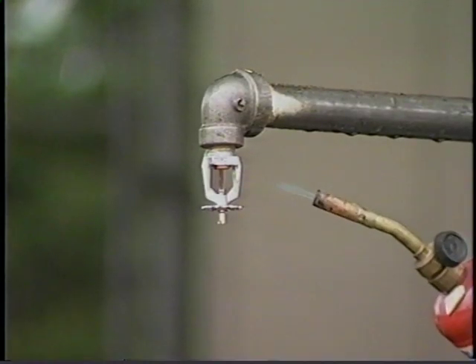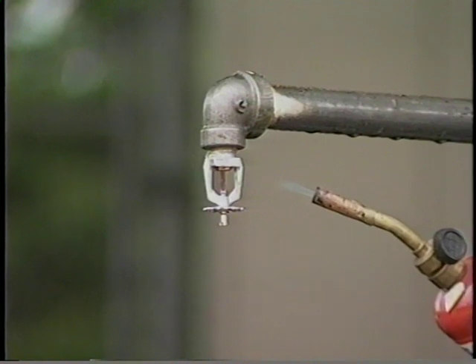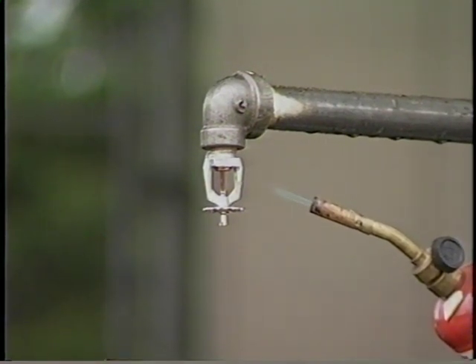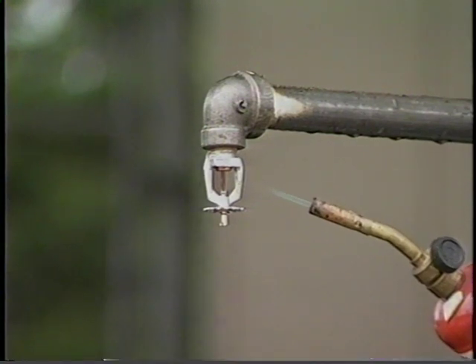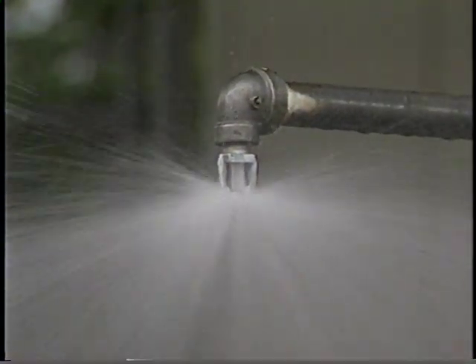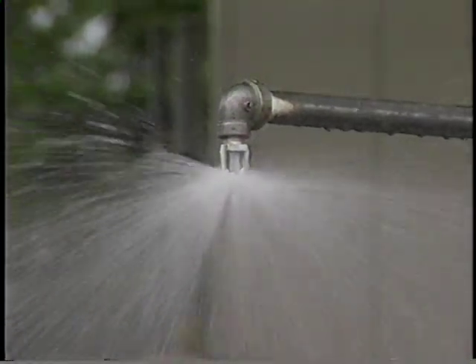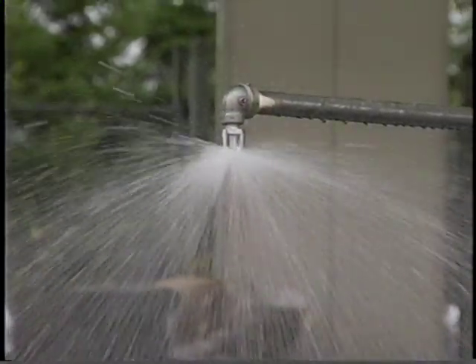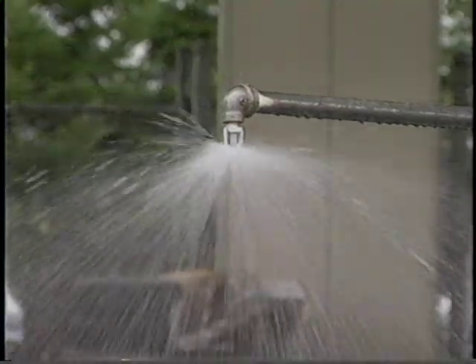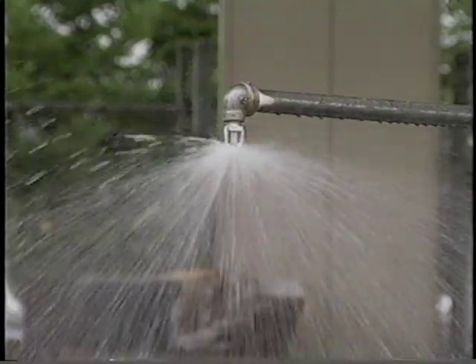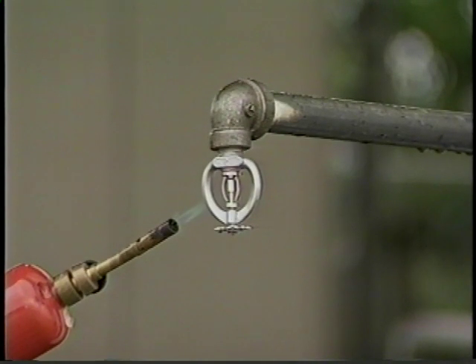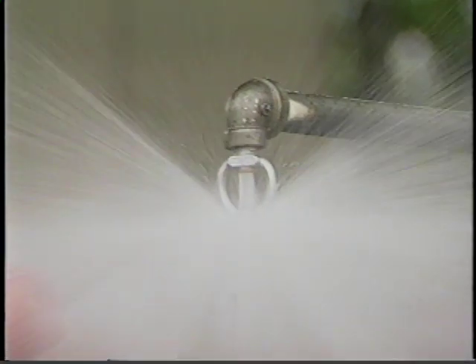Some sprinklers use a small bulb filled with liquid and an air bubble to hold the opening shut. Heat from the fire expands the liquid until the bubble is absorbed into the liquid. This increases the internal pressure until the bulb shatters, releasing the valve cap. The breaking temperature is regulated by the amount of liquid and the size of the bubble in the bulb. Another device is the chemical pellet. A pellet of solder, when placed under compression within a small cylinder, will melt at a predetermined temperature. This allows a plunger to move down and release the valve cap parts.